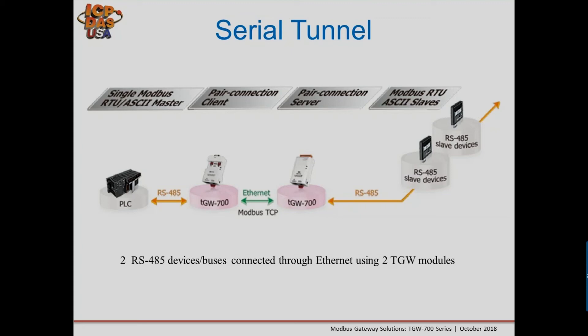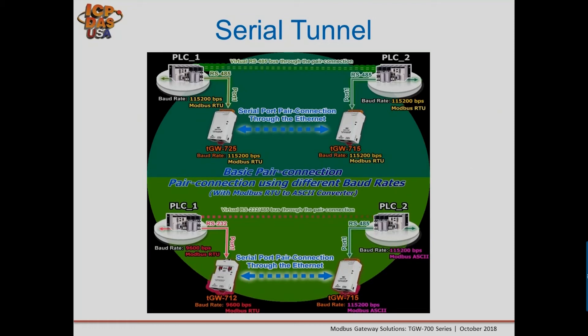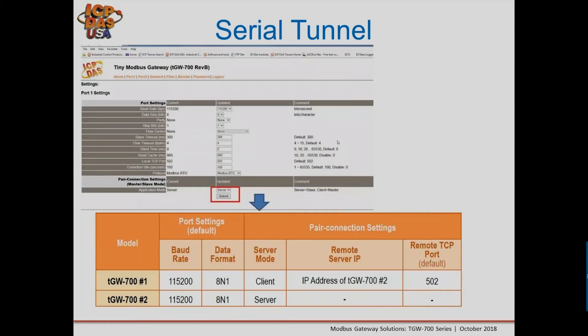For the serial tunnel setup, TGW module two is configured as the server with its baud rate set — just like a standard Modbus TCP to RTU application. TGW module one is configured in client mode, pointing to the IP address of TGW module two on port 502. Whatever comes in on one side of the bus comes out the other side — communication is paired one-to-one.